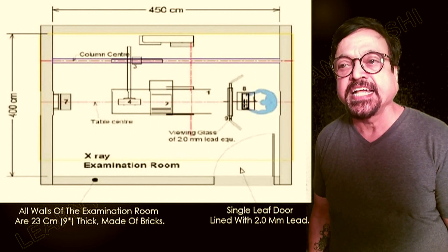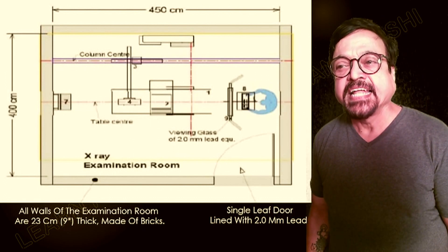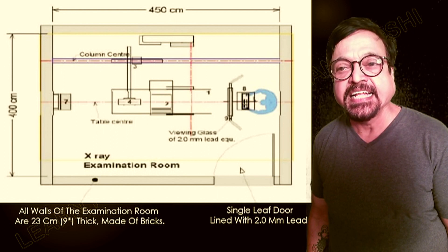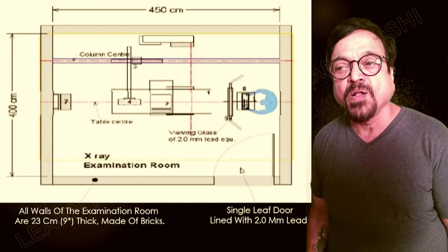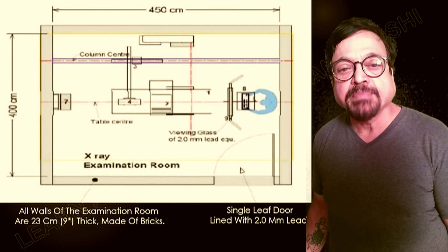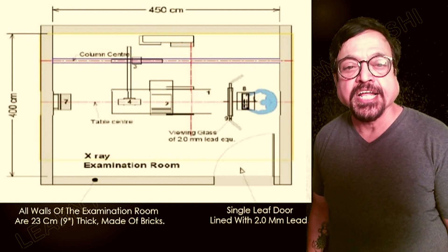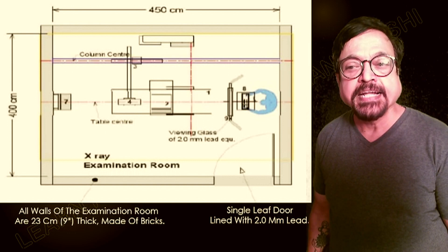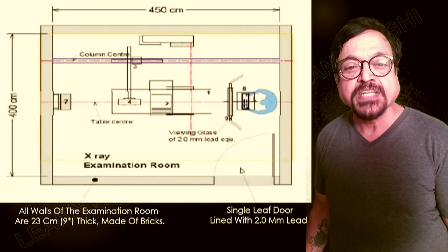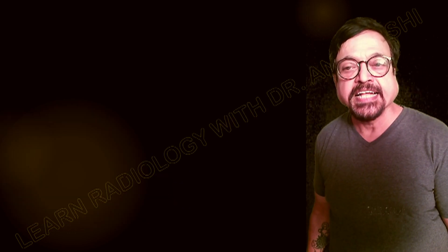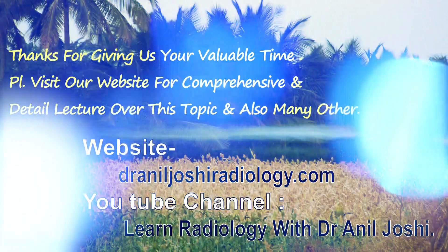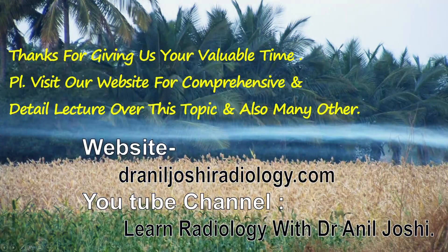Here you can see how an x-ray room is laid out — there is the x-ray unit, the chest stand, and the wall thickness is shown. The entrance is clearly marked, and the primary radiation should never be directed towards any of the doors or windows; that is, the tube should not face these openings.